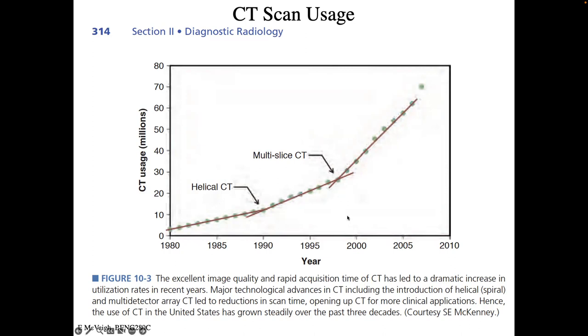Around that time, engineers started stacking CT detector rows: instead of one slice, why not four? Then eight, sixteen, sixty-four, and now 320 rows — essentially 320 CT scanners stacked on top of each other. When that happened, usage skyrocketed, because the scan could be done in 150 milliseconds with absolutely clear images.